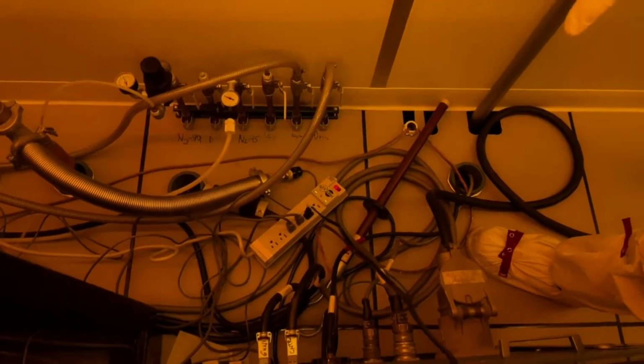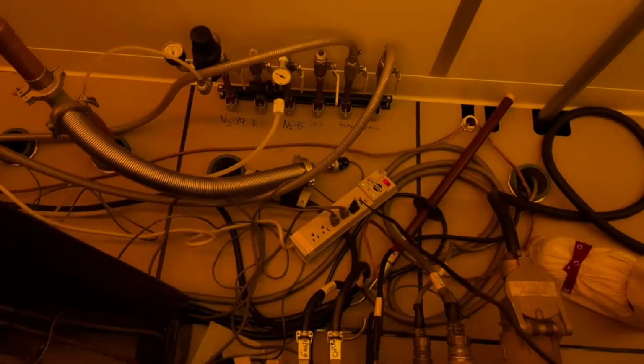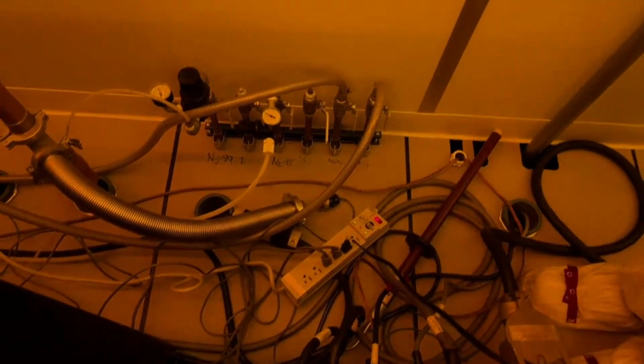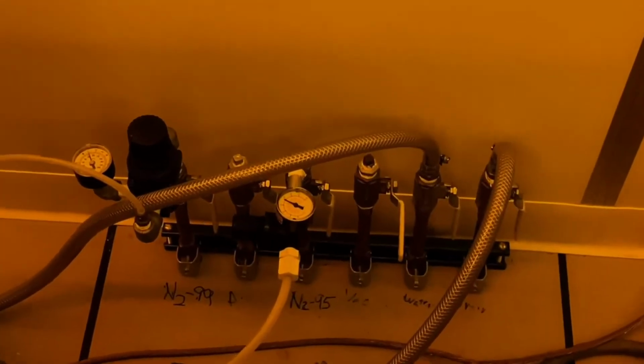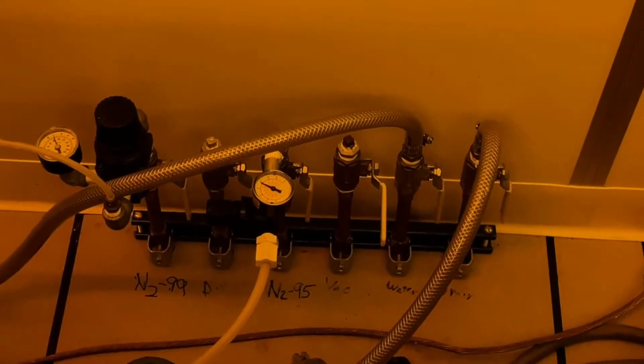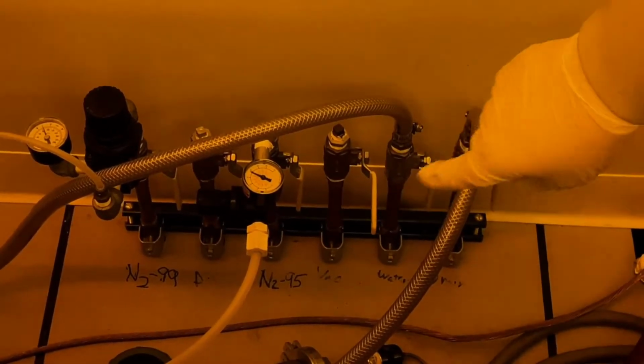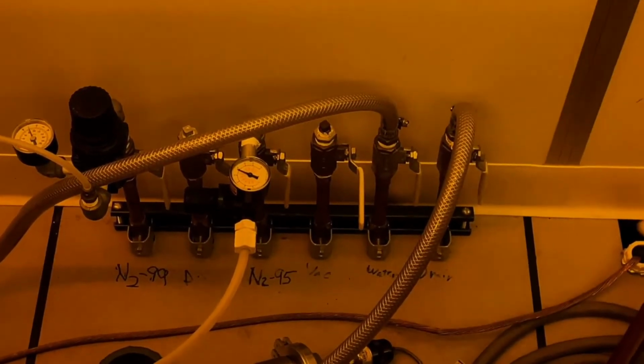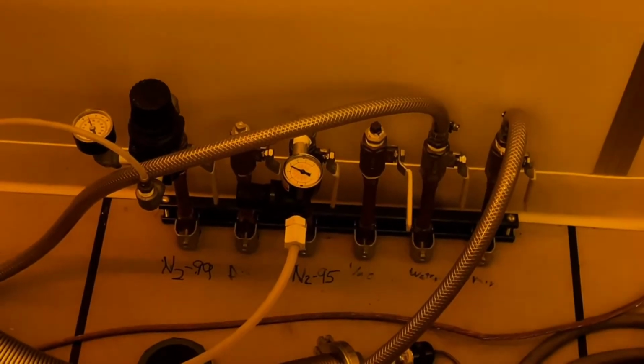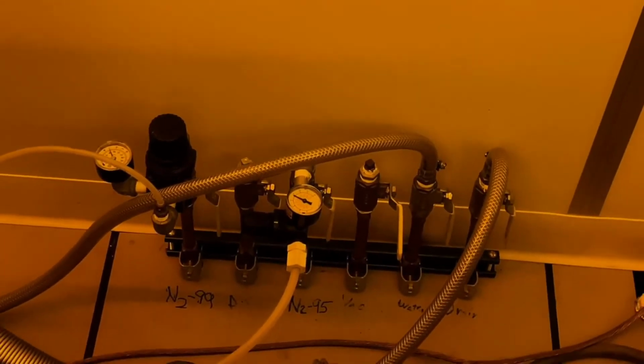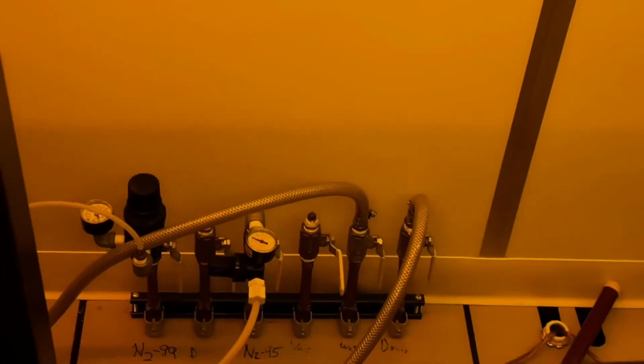Additionally, if you look in the back here, we have all of our gas and water sources for the system. Starting from the right, we have the drain cooling water, the positive cooling water, so it flows through the system to cool it. We have a vacuum that is not connected to anything, as you can see. Next, we have N95, nitrogen 95. This drives the pneumatics. So anything that's driven by pneumatic actuation comes from that source.